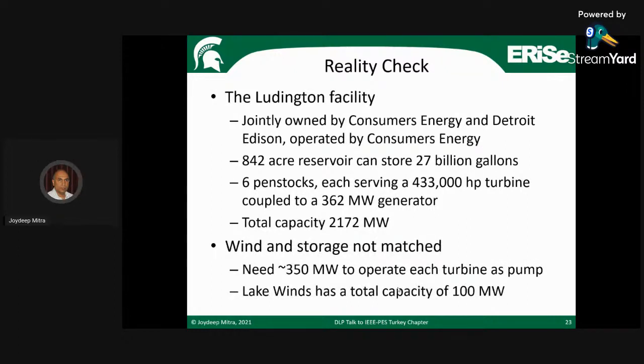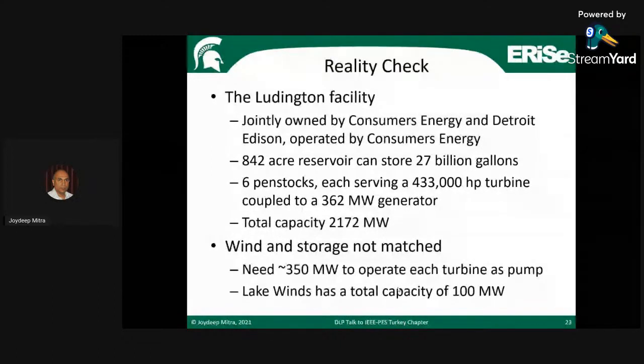But wind and storage are not matched, because you need about 350 megawatts to turn each turbine as a pump, whereas the whole wind farm has a total capacity of 100 megawatts. So this doesn't work, but careful sizing can work, and I'll tell you a little more about that in a minute.